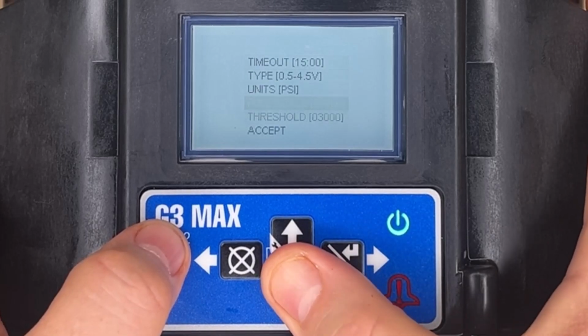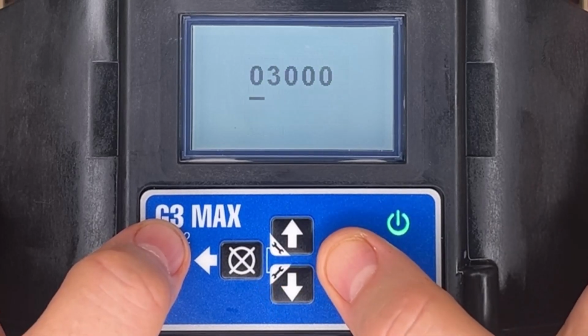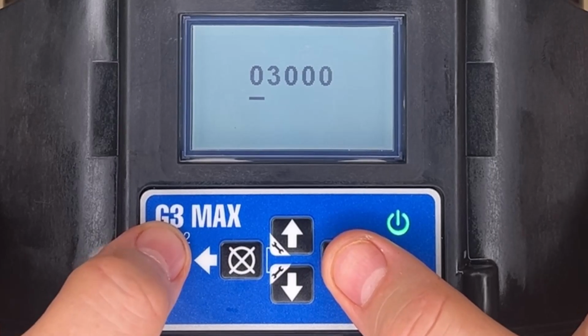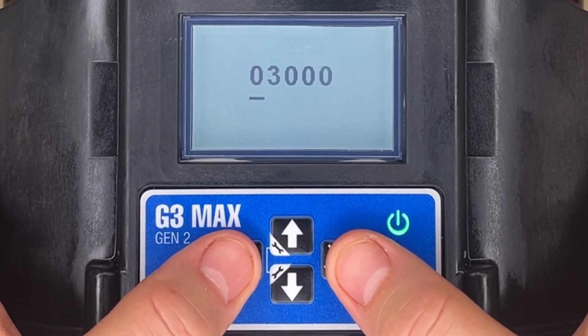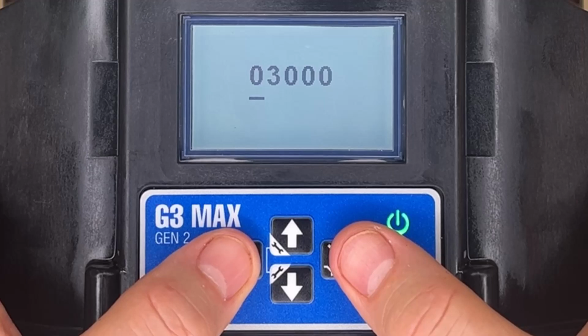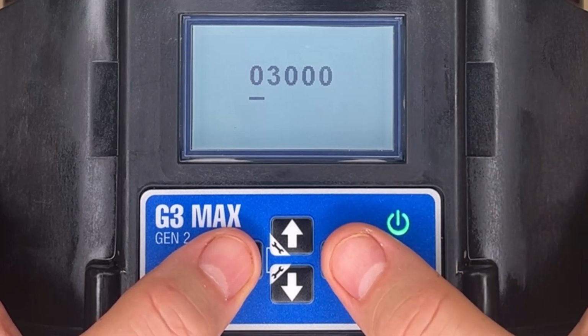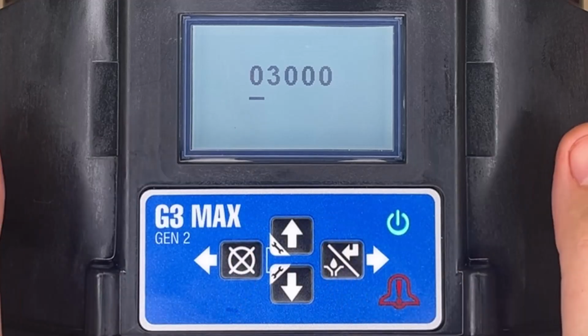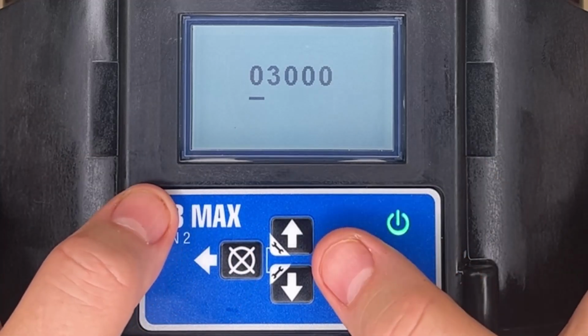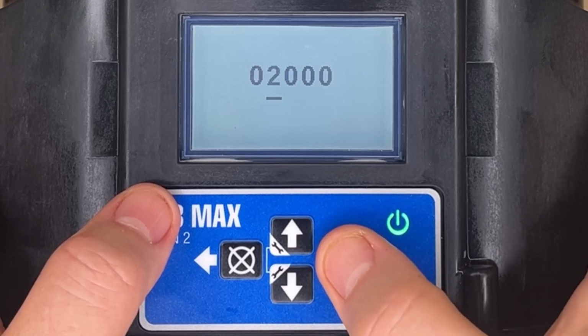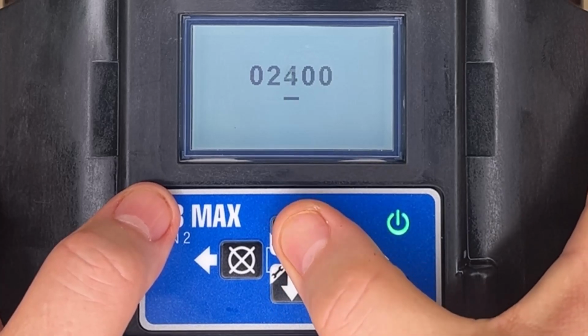And now threshold is where you actually want it to stop pumping. So the threshold is the same value that in the past you would have set on the pressure switch, either with some dials or maybe with a screwdriver. But in here now with a transducer, we can tell it what we want the threshold to be. And I'm going to change this to 2500 PSI.